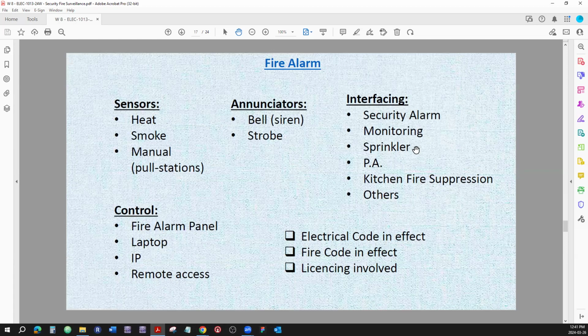And the pressure should be no less than whatever the amount is set. If the water pressure at the head end of the sprinkler system goes lower, then that means that one of the sprinkler heads was probably triggered and the water is just gushing out of it. So then the whole pressure drops. Then things trigger, right? The sprinkler system can be connected to the fire alarm or security alarm, or it could have circuitry on its own. And the communicator is triggered, so the monitoring station is notified, and fire trucks are dispatched. Sometimes the city pressure goes so low that it actually triggers the sprinkler system head end, so that sometimes could be a problem, right?